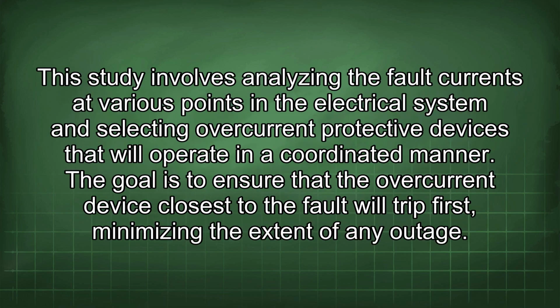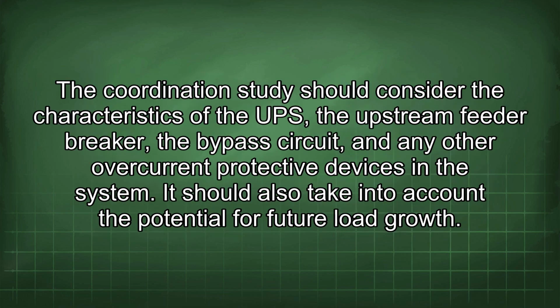This study involves analyzing the fault currents at various points in the electrical system and selecting overcurrent protective devices that will operate in a coordinated manner. The goal is to ensure that the overcurrent device closest to the fault will trip first, minimizing the extent of any outage. The coordination study should consider the characteristics of the UPS, the upstream feeder breaker, the bypass circuit, and any other overcurrent protective devices in the system. It should also take into account the potential for future load growth.